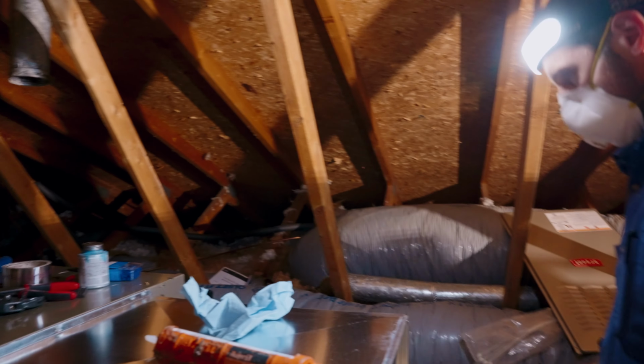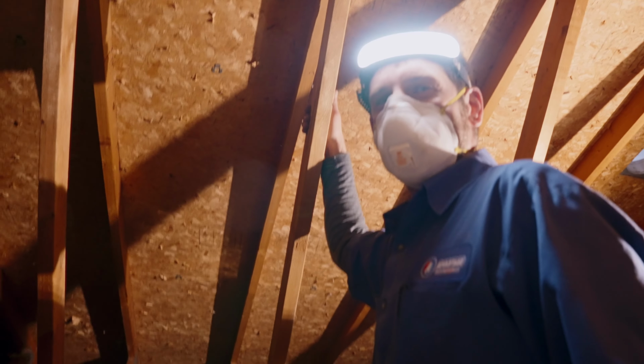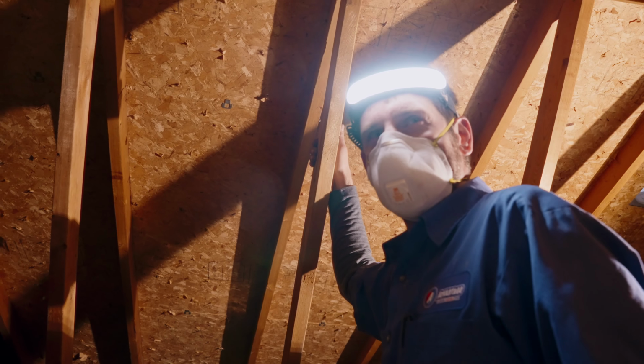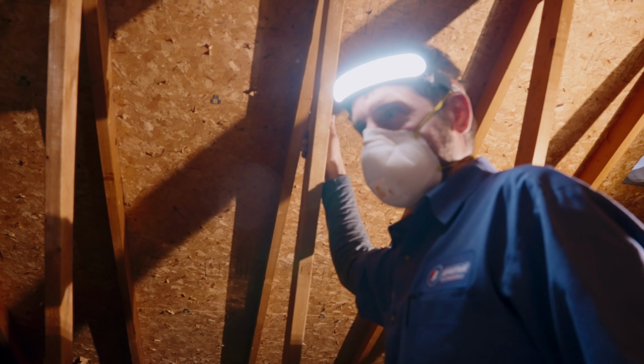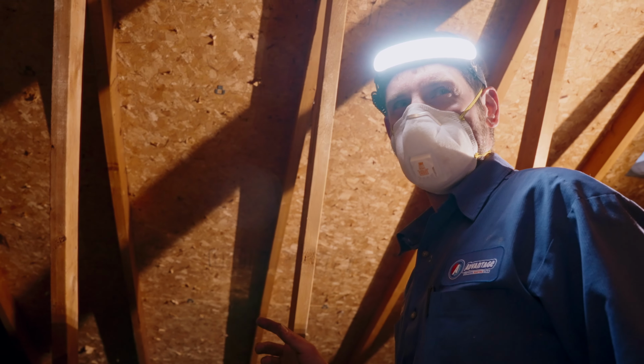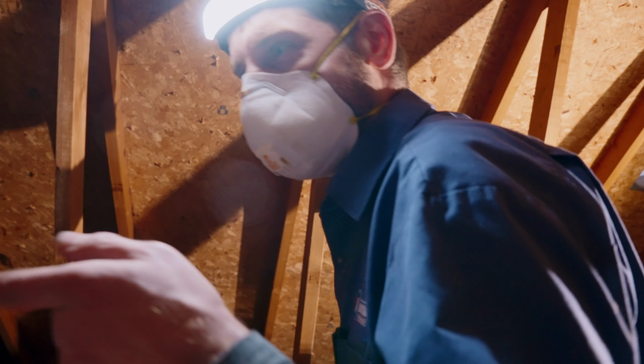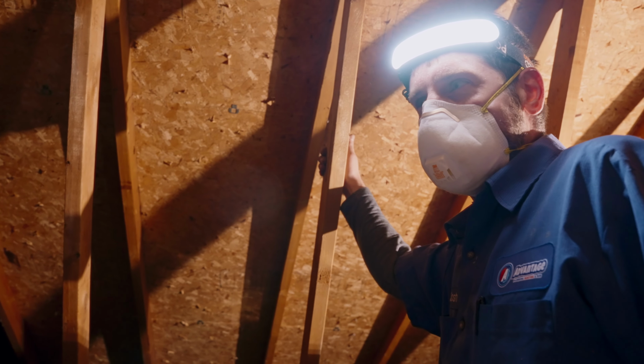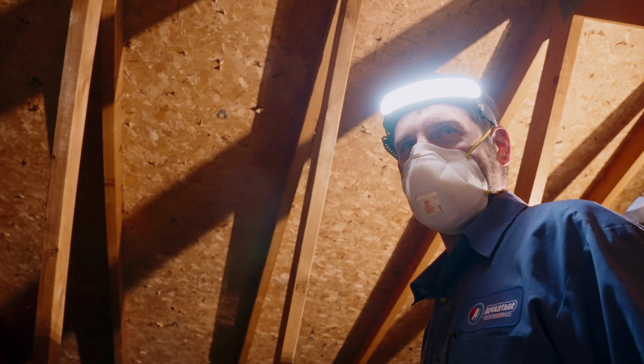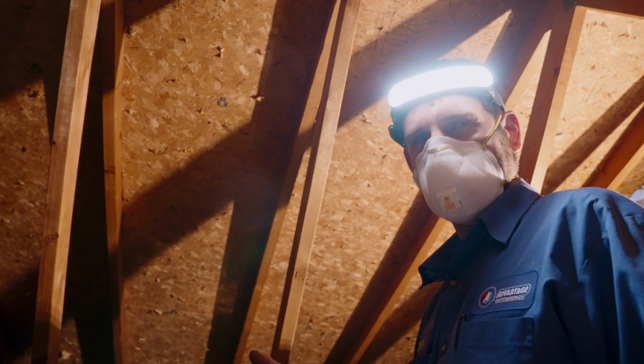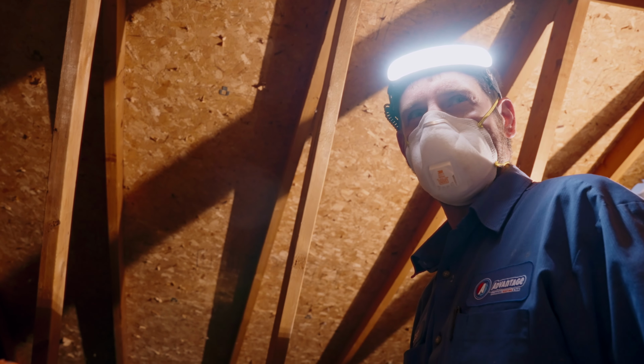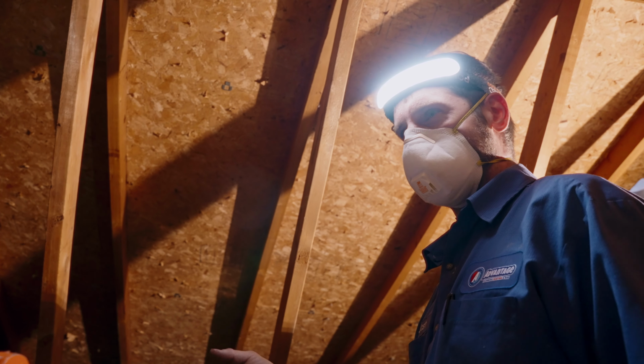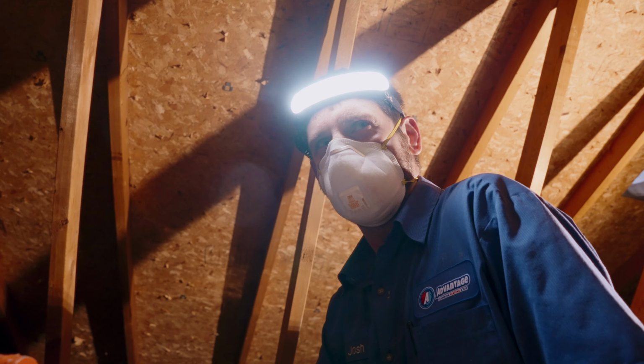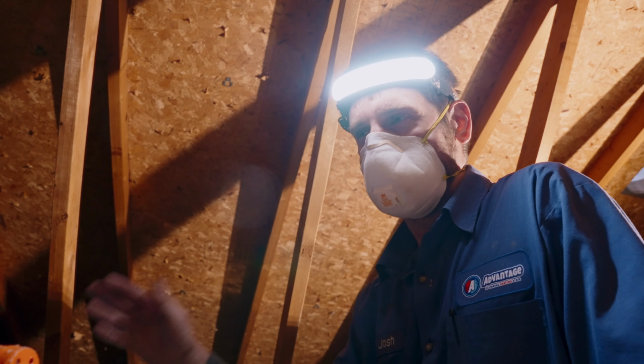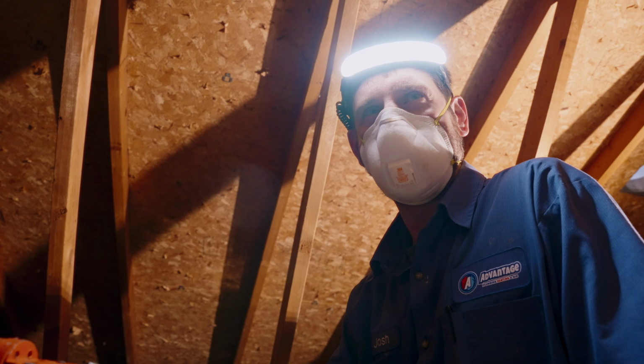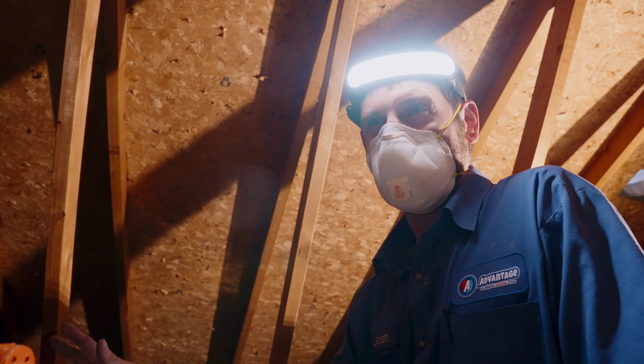What was going wrong with the last furnace in this building? The furnace was very old and had a cracked heat exchanger. It had very bad flame rollout. When I first got here, someone had the gas off to it, and you could tell they just replaced the burner assembly, and there was just piles and piles of rust up in the heat exchanger. And then on the back of it, you could see where there's a bunch of flame rollout, which all signs are pointing straight towards the hole in the heat exchanger, which is very dangerous.